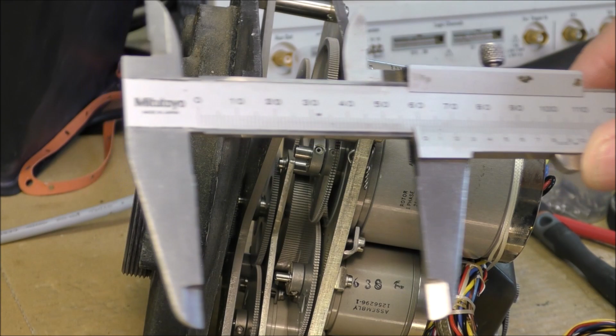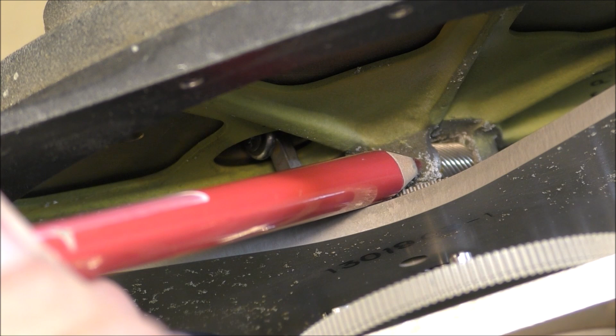6 centimeters. Okay, so this is a transmitter. We can see the mechanism which permits to adjust the output. There is a roller here, which is attached to this lever. The deformation of the plate permits a small rotation of the shaft depending on the screws, and the variation of the angle of this helicoidal gear is transmitted to the output shaft.